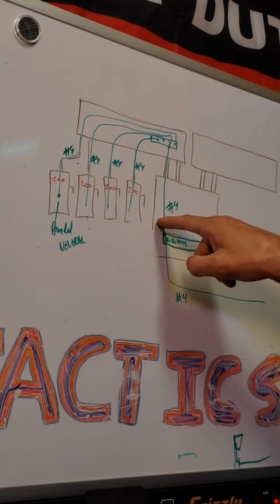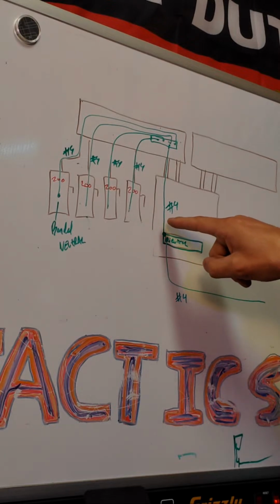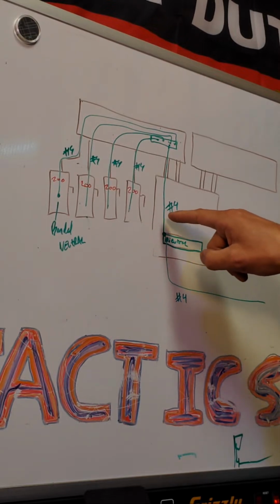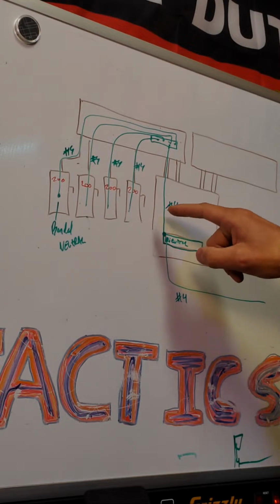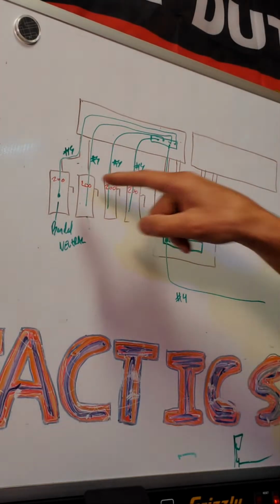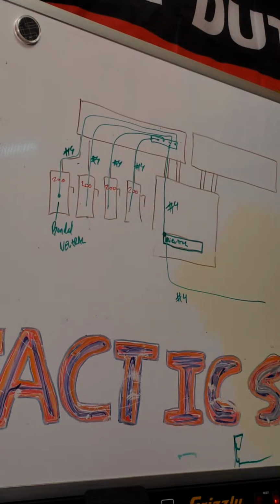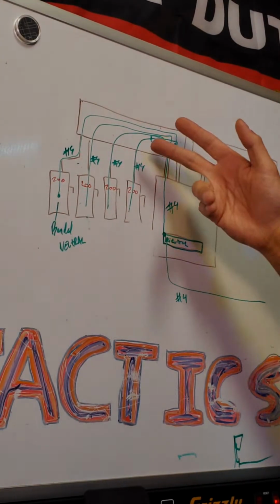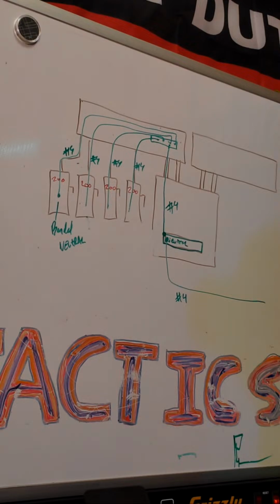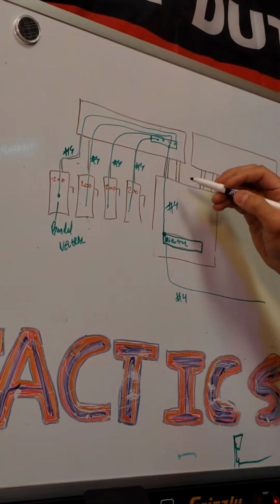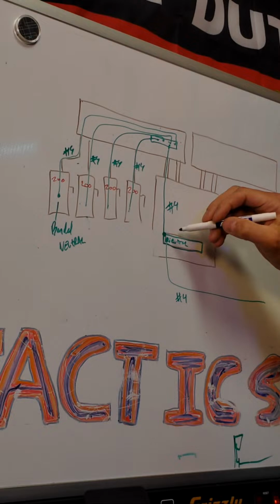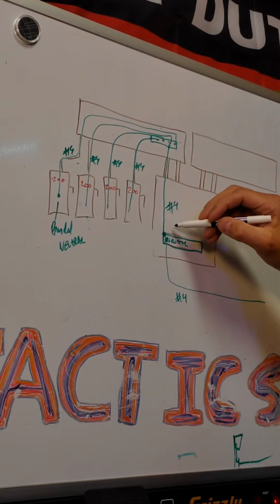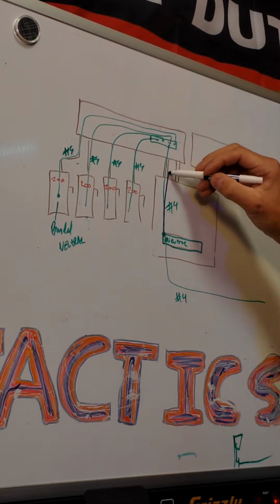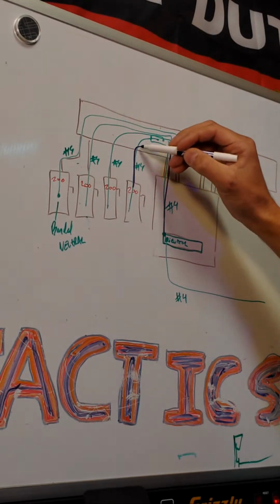I pointed to the electrician. I said, you know what? That's actually a neutral. It's not a service ground. You've got a number 4 neutral on a 200 amp service. You've also got a number 4 service ground, and you've also got a 2-aught neutral. So they had their neutrals going through. The neutrals were 2-aught. And as they should be, you can size it, 70%? You can downsize your neutral a little bit. So they ran the neutral up there too, to each one, right?